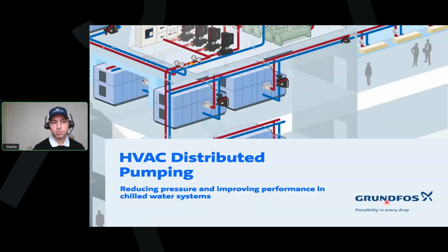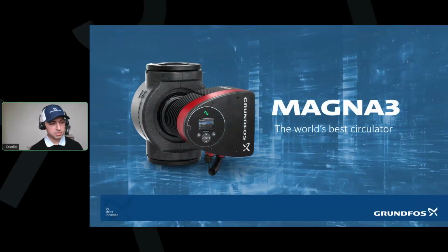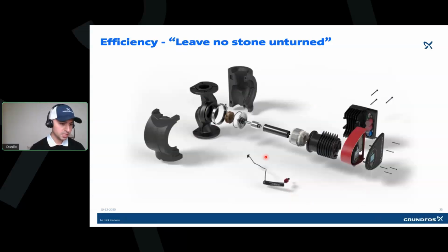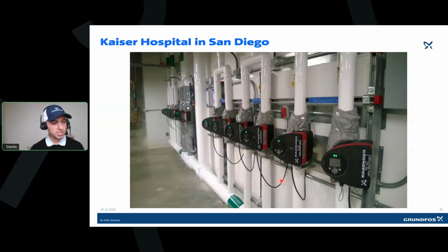Now, this is a more holistic approach, and I cannot talk about it without talking about one of the Grundfos pumps, which is our circulator. The reason I'm talking about this pump is because of the sensor the pump has. So now the pump already comes, this is what we're going to call an ECM motor, a smart pump with a differential pressure sensor, or it can also be utilized as a differential temperature sensor, already standard with the pump. This is just an example, so you have an idea about size and how it looks. So we're talking about circulator pumps. This is a hospital in Southern California.